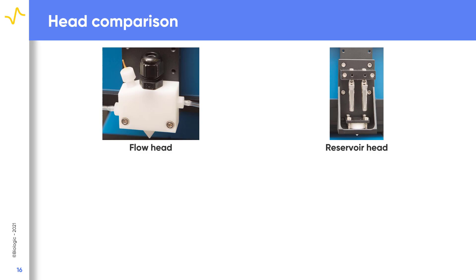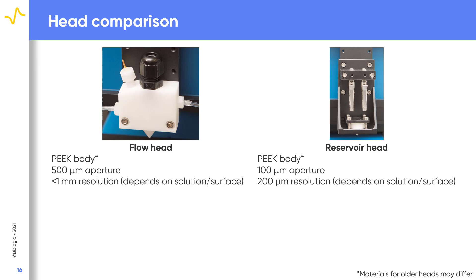How are the two heads supplied with the SDS 470 compared? Both heads are now made of PEEK for the highest chemical compatibility. The flow head has a 500 micron aperture resulting in a resolution better than 1 mm, though this is dependent on the solution and sample.